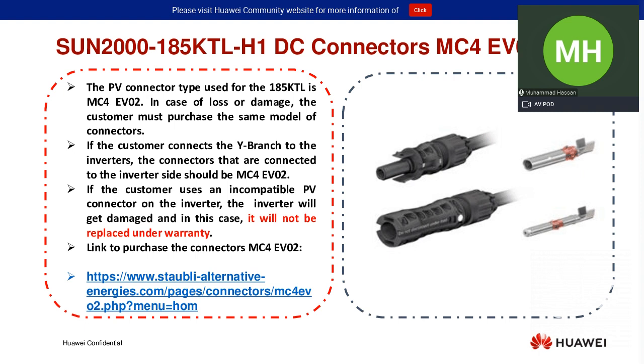These are the DC connectors, MC4 EV02. This is the type of MC4 connector we use on the string side of the inverters. We provide the correct number of DC connectors inside the inverter box, so you don't need to purchase DC connectors from the local market. Once you open the box, you will find the inverter, the user manual, the documents, and the DC connectors. The only things you need to purchase, as I mentioned before, are the crimping tool with the correct die, and the wrench tool, so that you can tighten the nuts on the DC connectors tightly, so that there will be no problem.